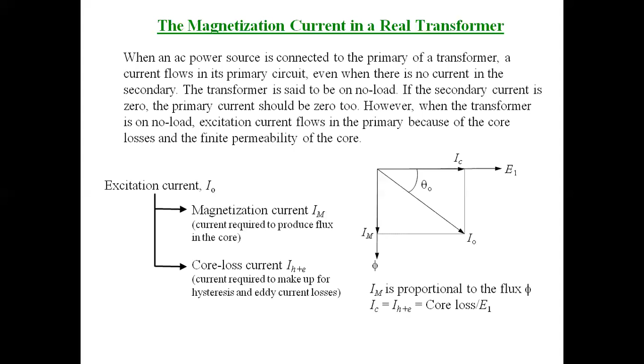So the excitation current is divided into two components. One is the magnetization component, which is the current required to produce and maintain the flux in the core. The next one is the core loss component, the current required to make up for hysteresis and eddy current loss. What is core loss? It is the combination of hysteresis loss and eddy current loss.